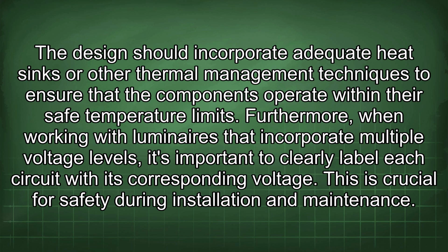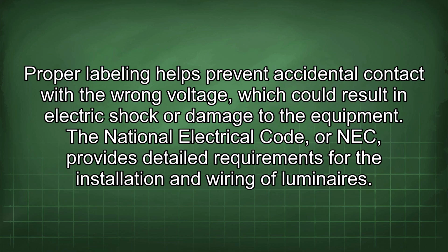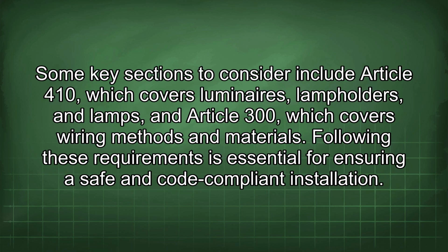Furthermore, when working with luminaires that incorporate multiple voltage levels, it's important to clearly label each circuit with its corresponding voltage. This is crucial for safety during installation and maintenance. Proper labeling helps prevent accidental contact with the wrong voltage, which could result in electric shock or damage to the equipment. The National Electrical Code, or NEC, provides detailed requirements for the installation and wiring of luminaires. Some key sections to consider include Article 410, which covers luminaires, lamp holders, and lamps, and Article 300, which covers wiring methods and materials. Following these requirements is essential for ensuring a safe and code-compliant installation.